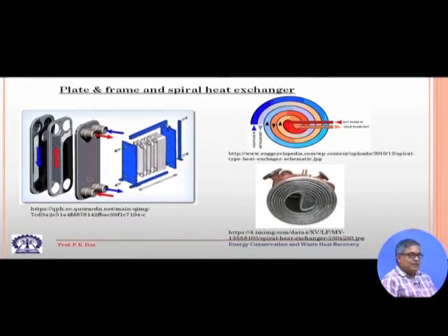There are certain limitations. These heat exchangers cannot withstand very high pressure, because there could be leakage from the gaskets, nor very high temperature. It is also suitable only for handling cleaner fluid, because the passages are very small and can get clogged by dirt etc., if the fluid carries that.